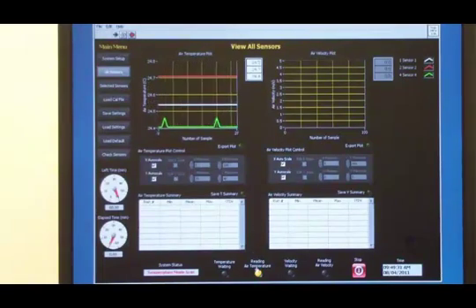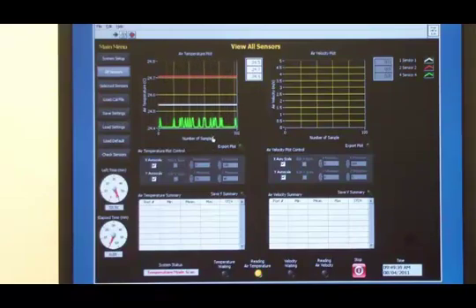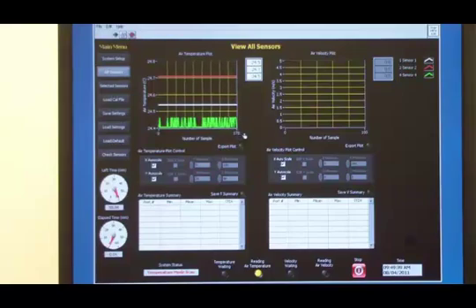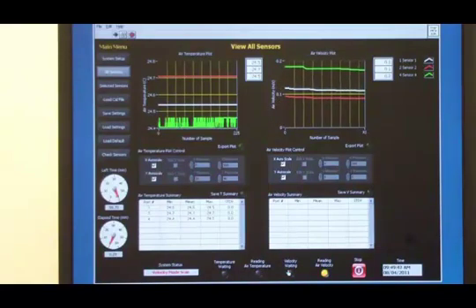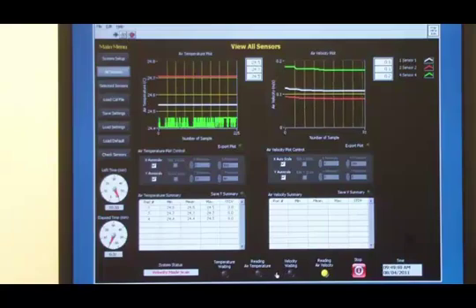You can see here, it's reading air temperature through our candlestick sensors. And we set it up to read about 500 or so points. Now it's switching over to velocity. Now the system automatically switches from air temperature or surface temperature to air fluid velocity. And here you see the velocity plots.